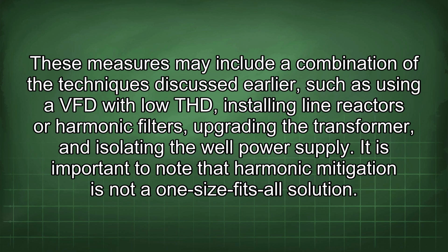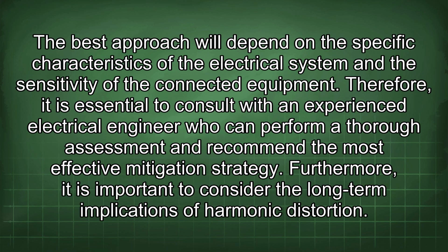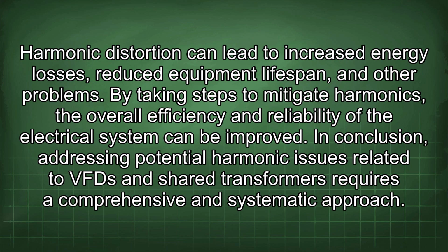It is important to note that harmonic mitigation is not a one-size-fits-all solution. The best approach will depend on the specific characteristics of the electrical system and the sensitivity of the connected equipment. Therefore, it is essential to consult with an experienced electrical engineer who can perform a thorough assessment and recommend the most effective mitigation strategy. Furthermore, it is important to consider the long-term implications of harmonic distortion. Harmonic distortion can lead to increased energy losses, reduced equipment lifespan, and other problems. By taking steps to mitigate harmonics, the overall efficiency and reliability of the electrical system can be improved.